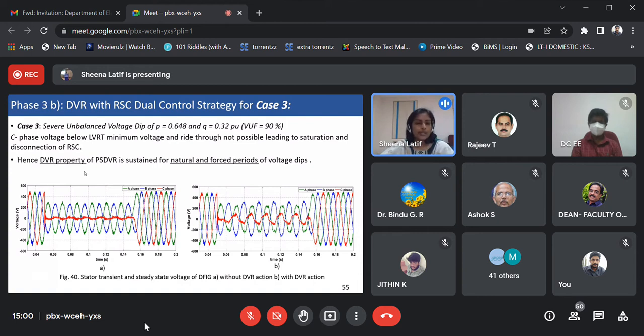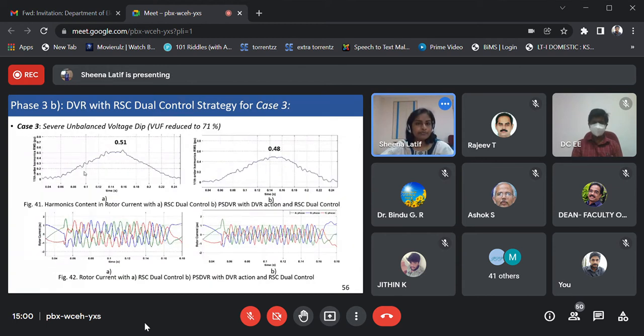Hence, since the LVRT condition will not be satisfied, the RSC will probably trip. So in order to provide ride-through for the RSC as well as the DFIG in this case, that is, VUF equal to 90%, the DVR mode is sustained during the steady state period as well as the transient period, and the resultant stator voltage after the DVR mode of action is shown here.